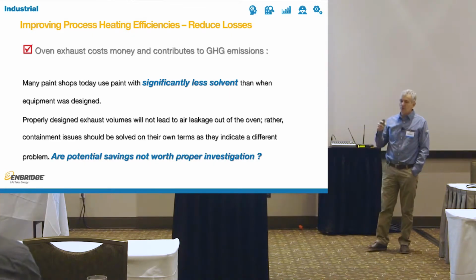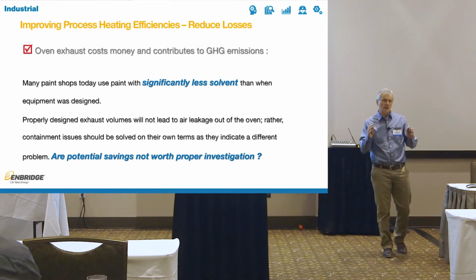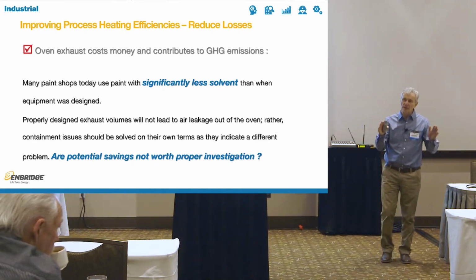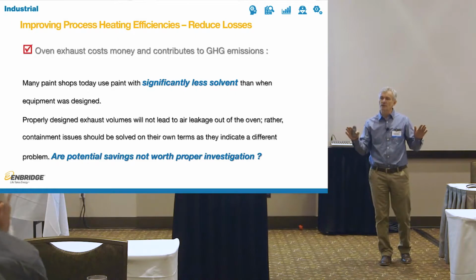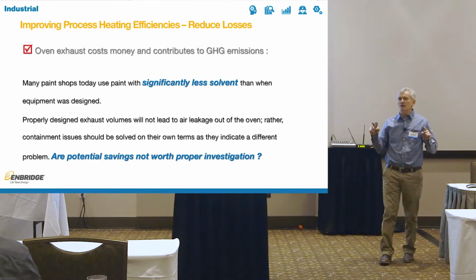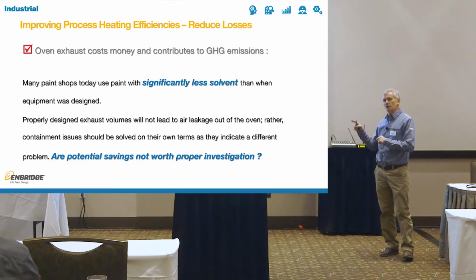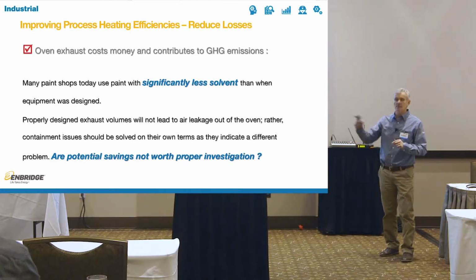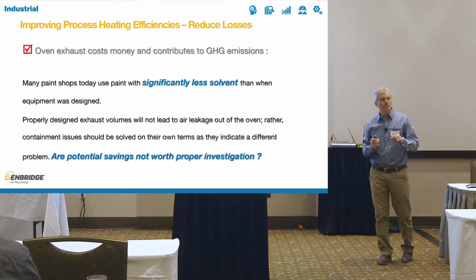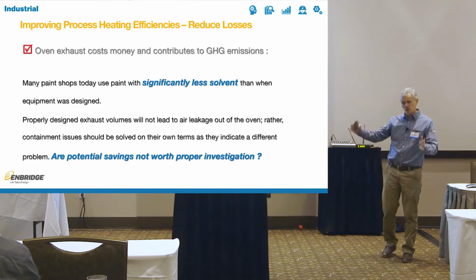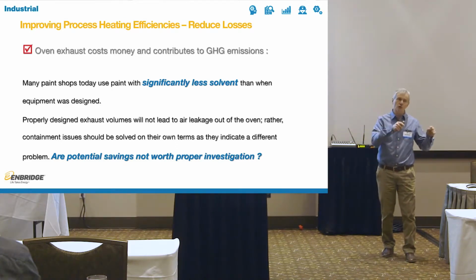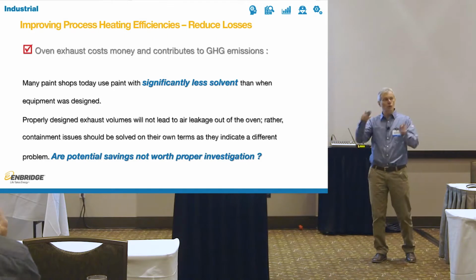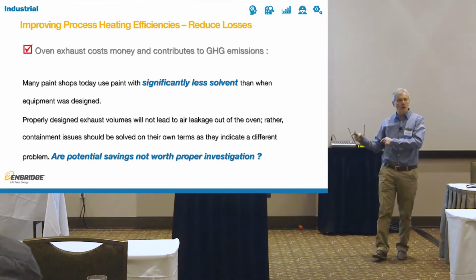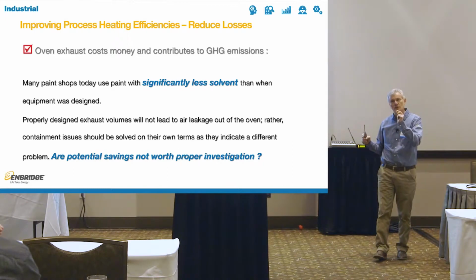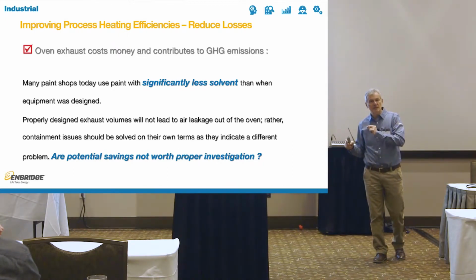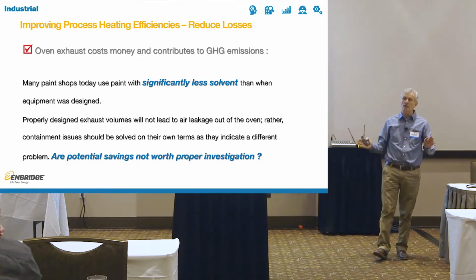The other thing that people are always worried about is that reduced exhaust will leave them open to leaking oven exhaust out into the facility. But you would be surprised how many of those places don't have that problem because of the oven exhaust, but because of the negative pressure in the building. I've had people say, no, my ovens are tuned for that condition. No, your ovens are tuned for that condition because you had that condition. They were not meant to go into that condition in the first place. Every oven is designed for ever so slight negative pressure, but that doesn't mean you have to fight a huge negative pressure around the oven.